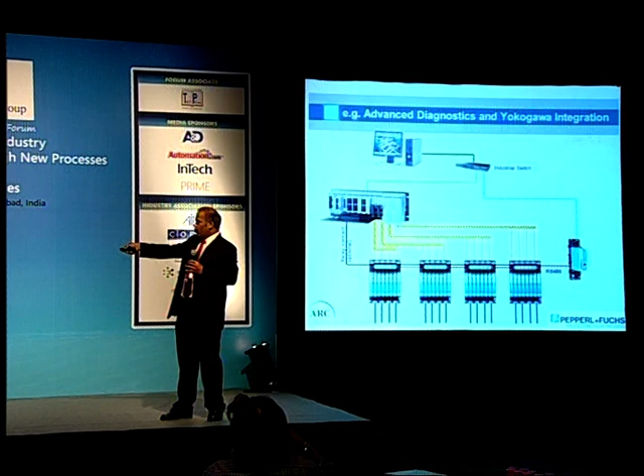Regardless of whichever DCS is being used, a similar type of integration is followed. The DCS asset management system indicates the number of devices connected as well as diagnostic information for that specific segment. If anything happens, it raises an alarm, opens the software, and tells exactly what happened, then tells the technician how to solve the problem and where it is.